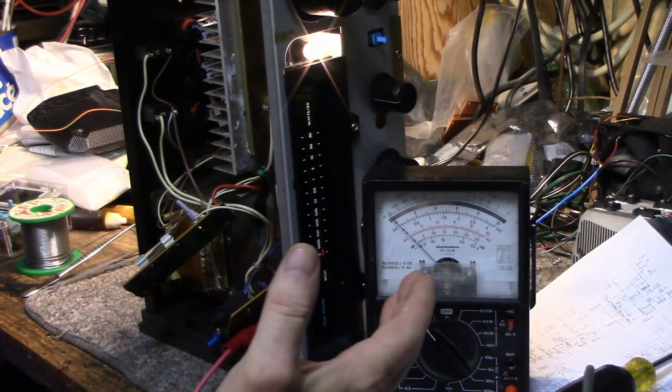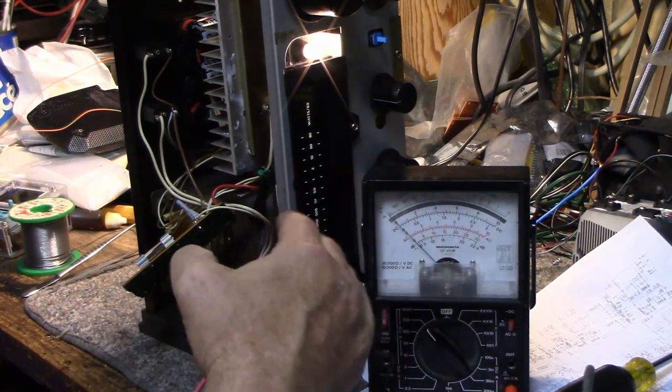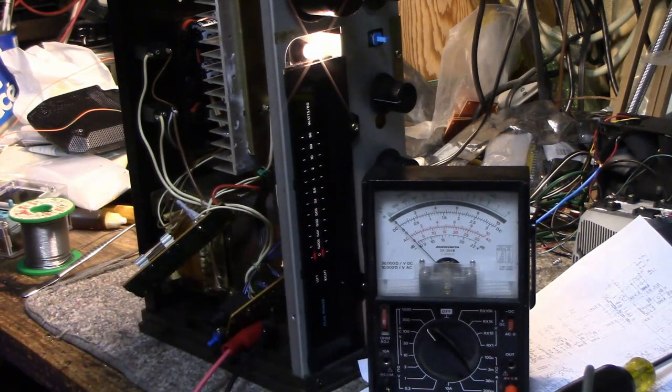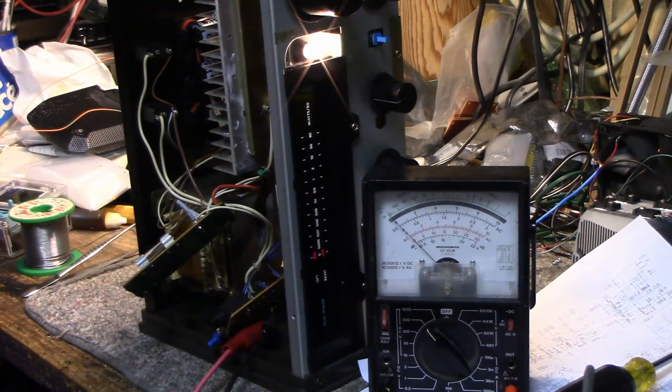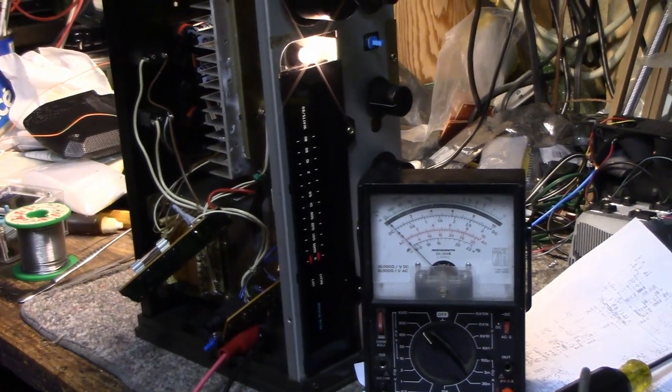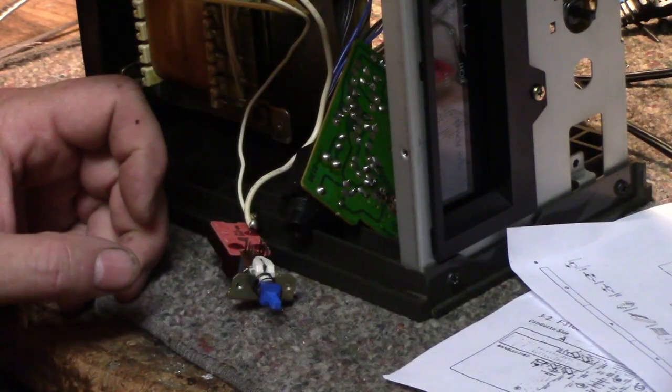So as it's arcing, you can definitely see the voltage rising across that switch that's supposed to be closed. When the switch finally does make contact, the voltage drops to zero. So that switch is bad.